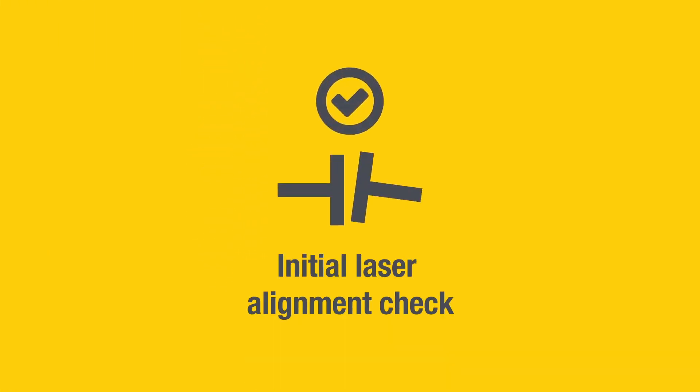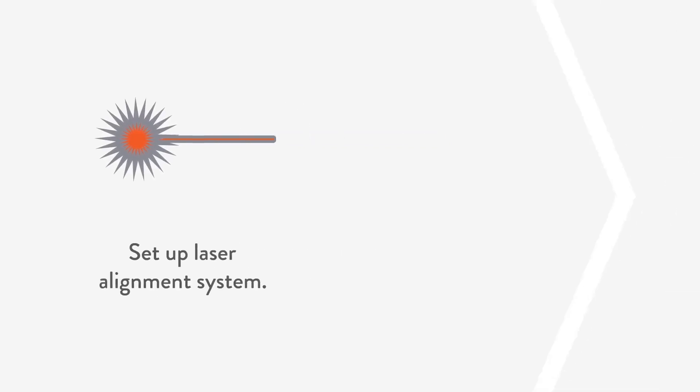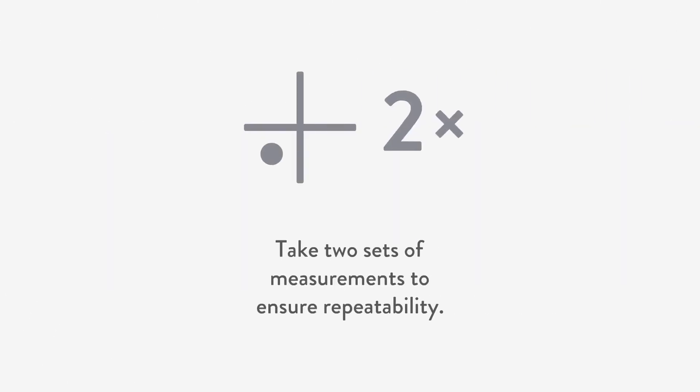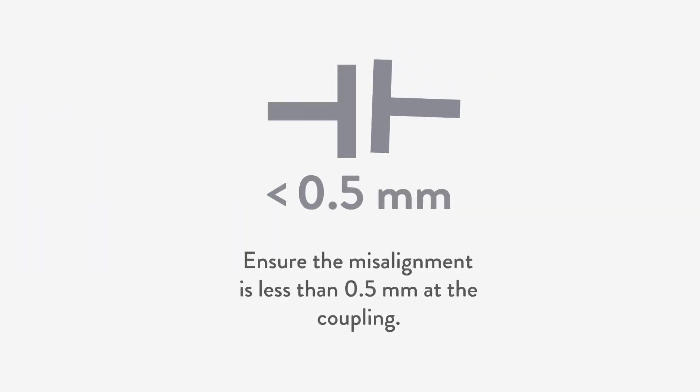Now it is time for step 3: the first alignment check with the laser system. Set up your laser alignment system. Take two sets of measurements to ensure repeatability. Ensure the misalignment is less than 0.5 millimeter at the coupling.